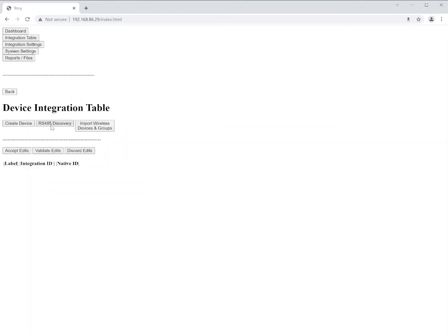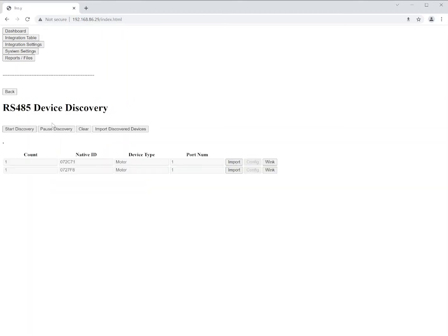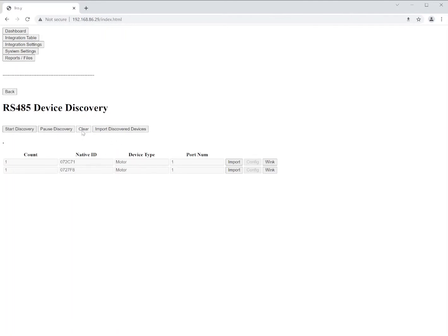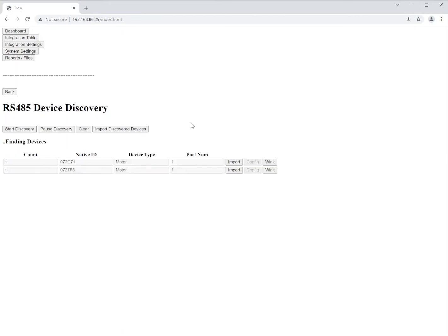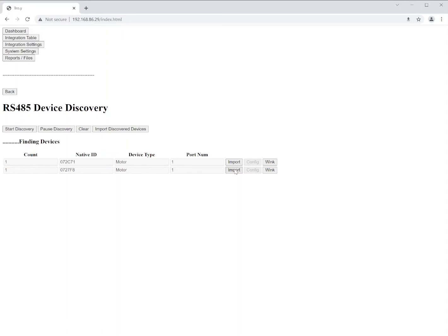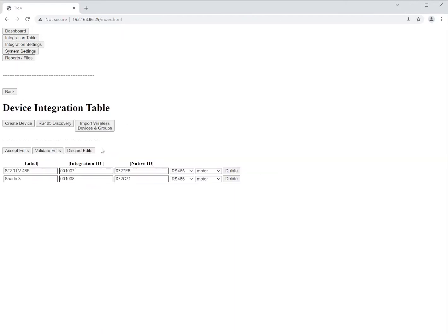The first thing we're going to do is we're going to start with the device table. We're going to click on device and we're going to click on RS-485 discovery. There's some already here, so we're going to clear that and then we're going to click discovery. What this is going to do is this is going to go out and find any devices that are currently connected to the RS-485 network. In this case, we have two motors found. In here we can create names for these devices, if we'd like to, and then we can import these devices as needed. We're going to stop the discovery and we're going to import these two devices.